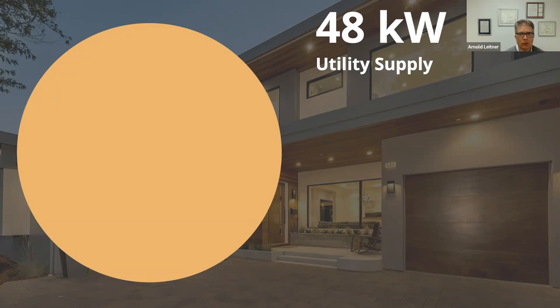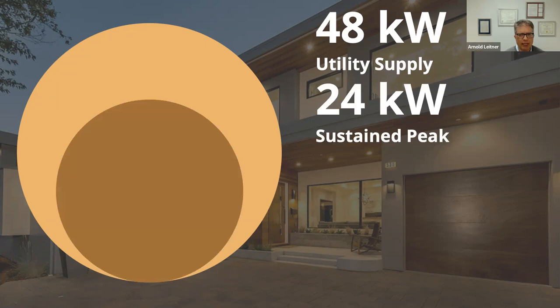So that is what the utility must cover, but really, on a sustained peak level, the kind of stuff that you can see on a utility bill on a 15 minute, 5 minute, or hourly level, you never usually go much beyond 24 kilowatts. As you saw earlier, that example was a load running at 17 kilowatts, but about 24 is about what you should plan for.